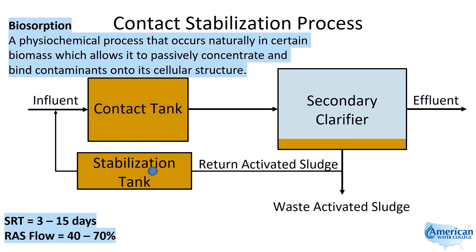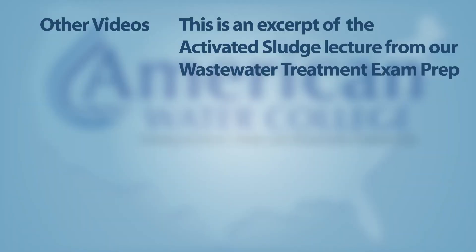The RAS flow is set in the range of 40 to 70%, so 40 to 70% of the activated sludge is returned and the balance is wasted.